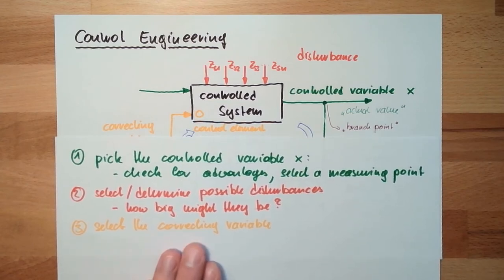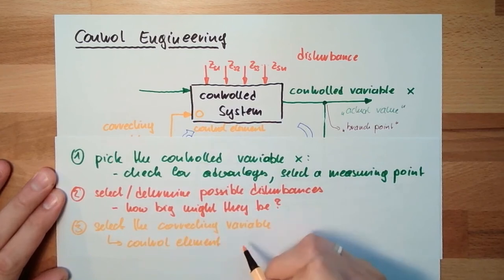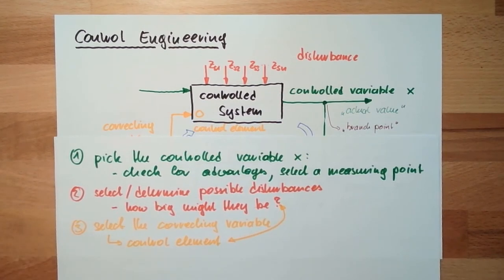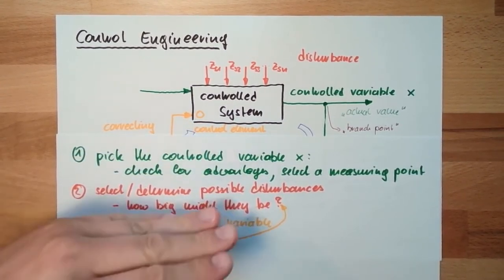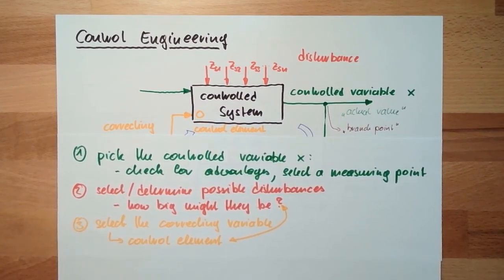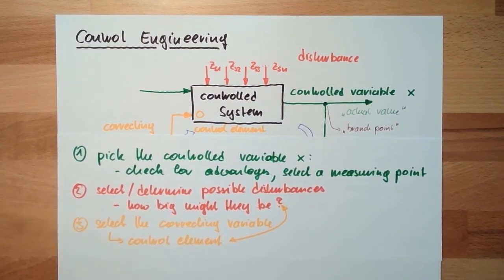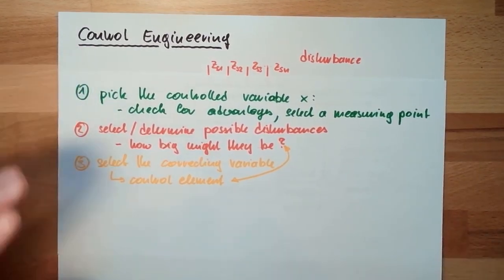Once I have selected the correcting variable, I can select the control element. I have to select it in a way that the control element is strong enough to correct the biggest possible disturbance. So from the correcting variable I know which type of control element I need, and from the disturbance I know how big and powerful this control element needs to be.